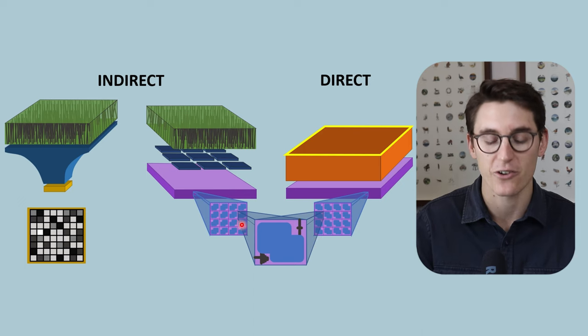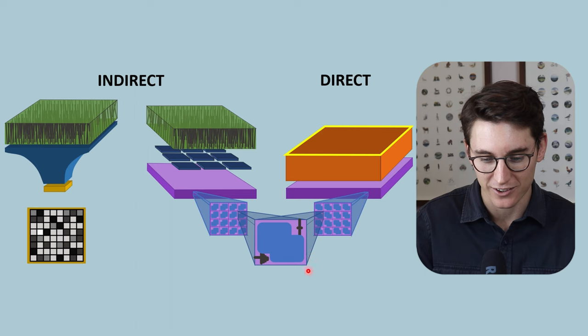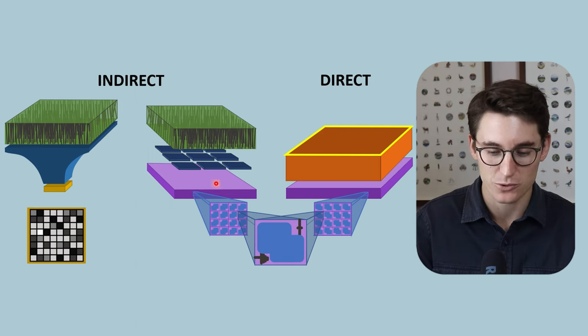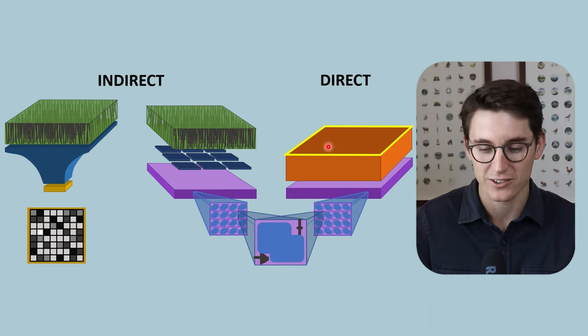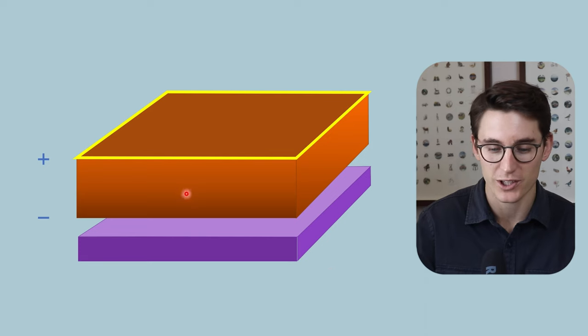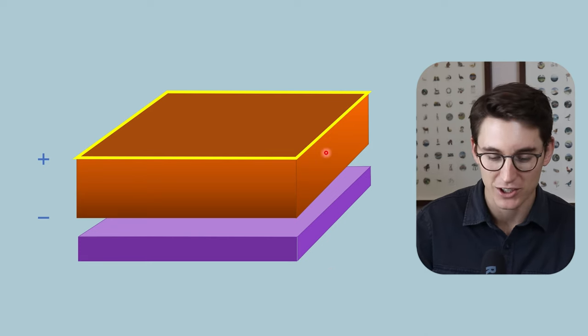And you can see from this diagram here, it shares a common detector element, a DEL. The same DEL that is used in our indirect thin film transistor array is used in our direct thin film transistor array. Now the difference here is that we use what is known as an amorphous selenium layer, and this is a semiconductor.